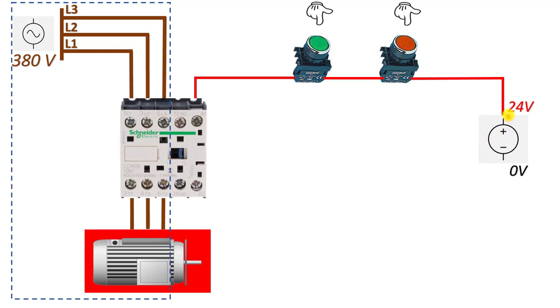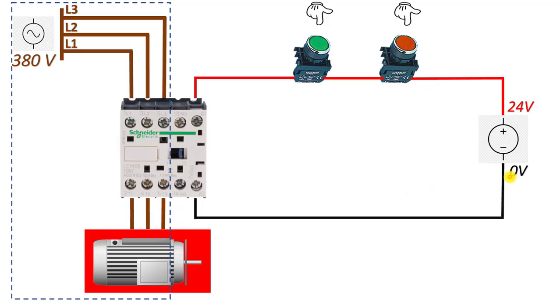To complete the connection, I connect the A2 pin to the neutral of the power supply, i.e., zero volts. My stop button is a closed contact, so the 24-volt signal passes through it. My start button is an open contact, so the 24-volt signal waits there. When I press the start button and send the trigger, my 24-volt signal enters from A1, exits from A2 to zero volts, completing the circuit and energizing the coil.